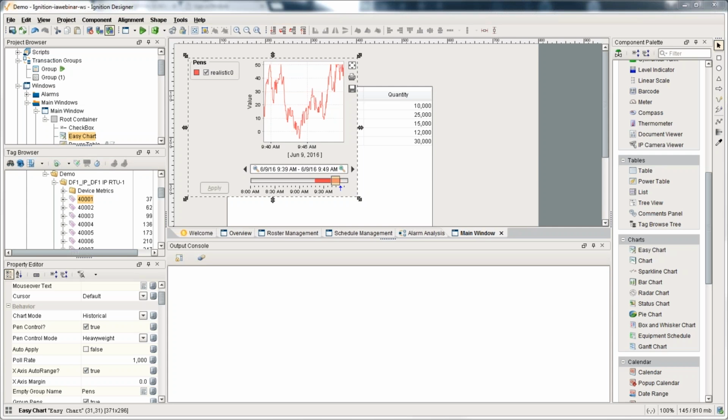If it doesn't, we have to be able to get to the data in some way, which means maybe a database backend, an ODBC connection that we can possibly get to, or an API, a REST or SOAP-based API. Whenever somebody asks me, can I connect to the system, the first thing I'm going to say is, yes, if it's a database, if it's OPC, HDA, or UA, if it is web services, or if we can get access to the data in a raw format like a file, then yes. Other than that, it may be very difficult to get those connections to work.